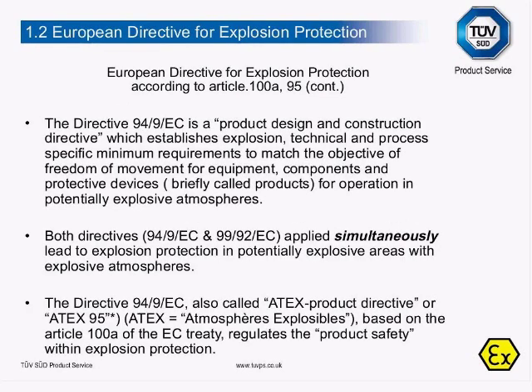Directive 94/9/EC is a product design and construction directive which establishes explosion, technical and process-specific minimum requirements to match the objective of freedom of movement for equipment, components and protective systems — briefly called products — for operation in potentially explosive atmospheres. Both Directives, 94/9/EC (the product) and 99/92/EC (the user), applied simultaneously lead to explosion protection in potentially explosive areas with explosive atmospheres, meaning that the two directives, although separate, will need to be interlinked together. Directive 94/9/EC is also called ATEX Product Directive or ATEX 95, based on Article 100A of the EC Treaty, and regulates product safety within explosion protection.